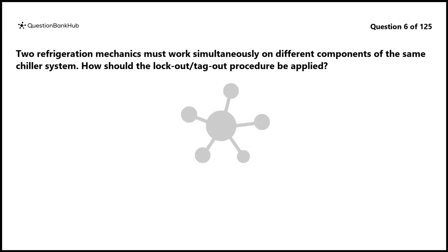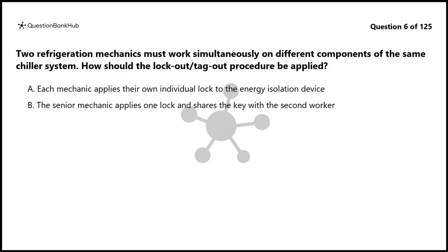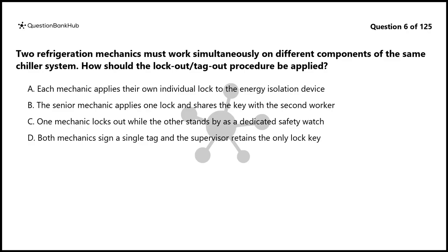Question 6. Two refrigeration mechanics must work simultaneously on different components of the same chiller system. How should the lockout-tagout procedure be applied? A. Each mechanic applies their own individual lock to the energy isolation device. B. The senior mechanic applies one lock and shares the key with the second worker. C. One mechanic locks out while the other stands by as a dedicated safety watch. D. Both mechanics sign a single tag and the supervisor retains the only lock key.